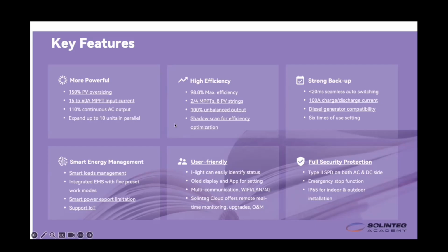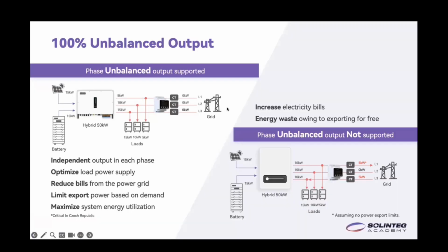So the next part is about high efficiency. First, our inverter can support up to 98.8% maximum efficiency, and that means you can get more power from the PV side. And here we can also support 100% unbalanced output. We can see the slide over here. First, we can compare two situations: where the inverter cannot support unbalanced output, or where we use our inverters that support this function. Well, first, let's take a look at this diagram over here.